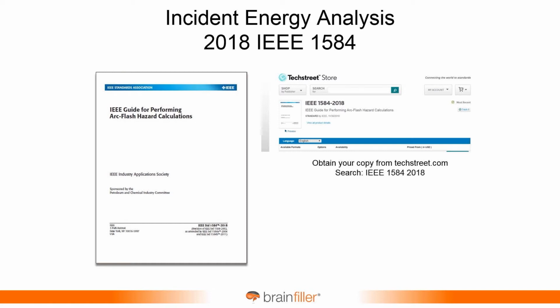So this is part of the incident energy analysis, and it wouldn't be complete if I didn't have at least one video showing an arc flash. And so this video that you're about to see is an arc flash that I staged. It was part of a pretty big project years ago. It was 50,000 amps of short circuit current, 480 volts. It was a really large switchboard. So let's see what this looks like.